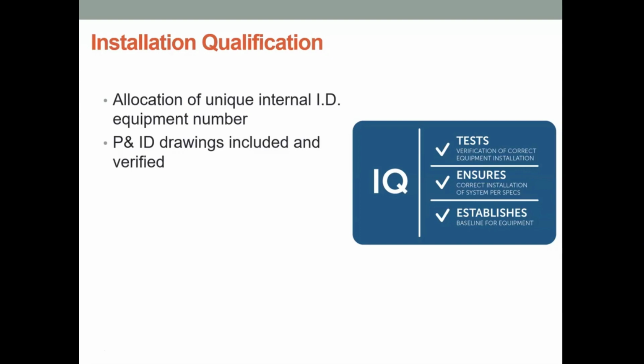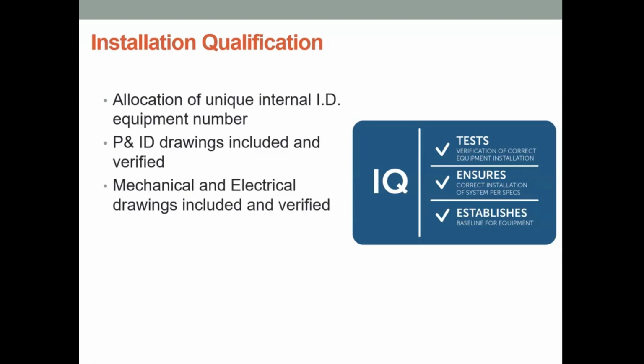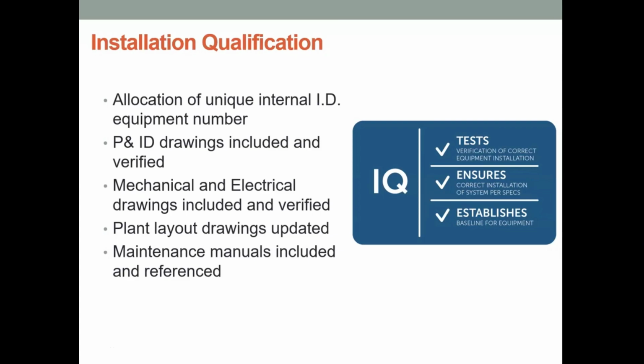Have the P&ID drawings been included and are they verified to be correct? Have your mechanical and electrical drawings been included and have they been verified to be correct? Have your plant layout drawings been updated to include this new piece of equipment? Have your maintenance manuals been included and have they been referenced and have they been properly stored and filed? And have you verified that the correct version of the software is in place and it's up to date and it's been qualified?